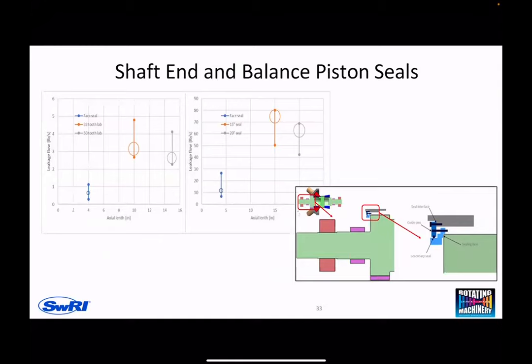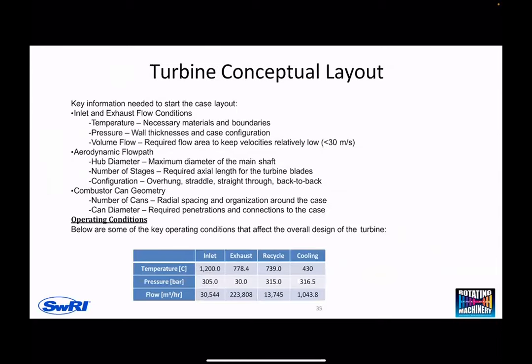What we end up going with in this system, instead of using a rotating seal like a face seal, we're going with a labyrinth seal with capture near the exit. We will have a recapture and reinjection system that will pull low pressure CO2, almost creating a vacuum. You pull CO2, some air, they will be separated and then reinjected into the system, so you have a net zero, or zero emissions, from the whole system.